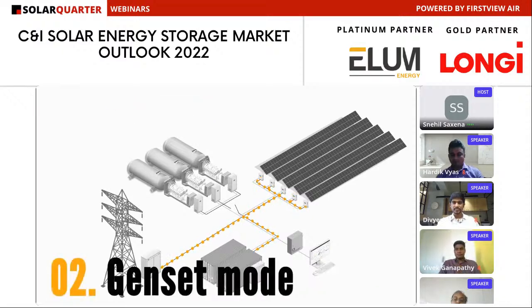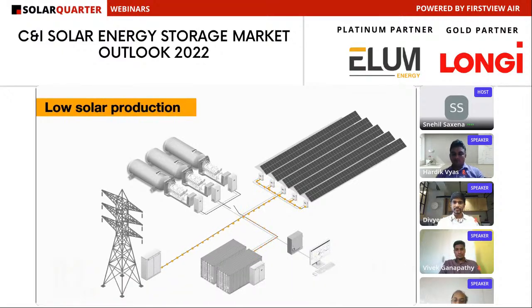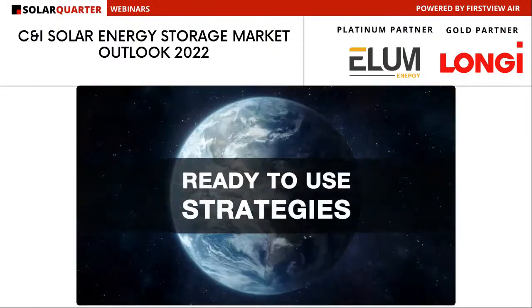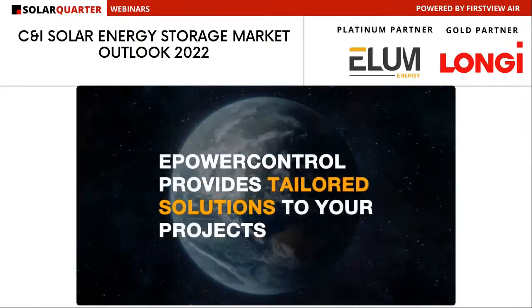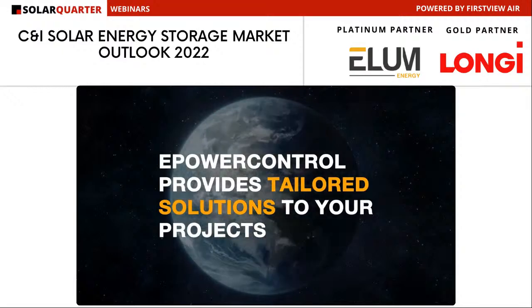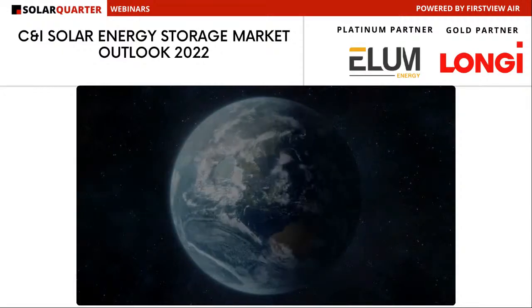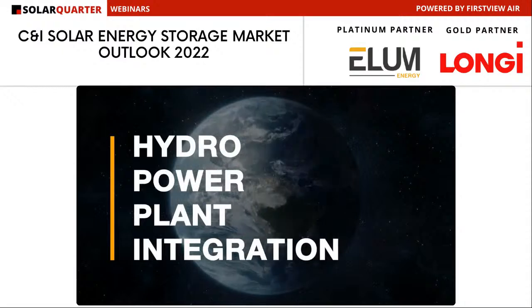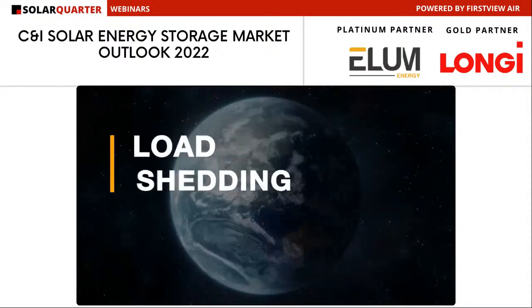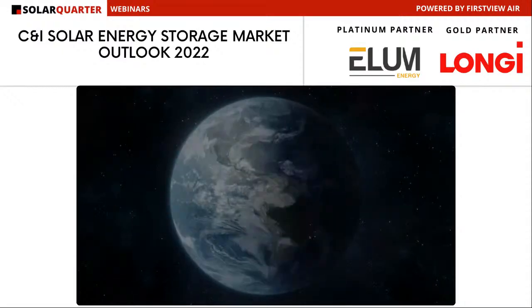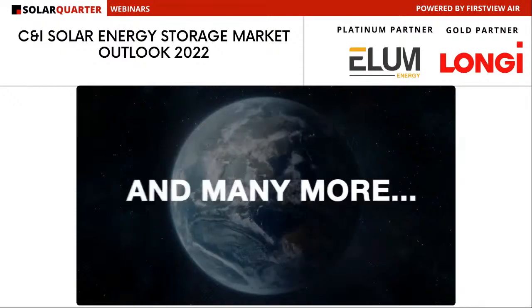When the conditions for battery mode are not met, the EPower Control MC enters genset mode. Third-party genset controllers are turned on and become the new regulation unit in the microgrid. Other ready-to-use strategies can also be deployed based on the specificities of your site. Elum Energy provides custom adaptation to all projects, including hydro power plant integration, load shedding, quiet hours, fixed power mode for grid injection, and many more.